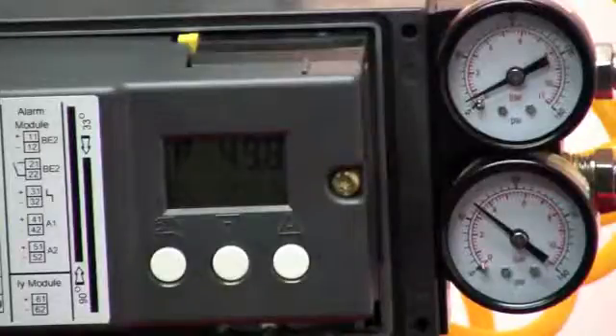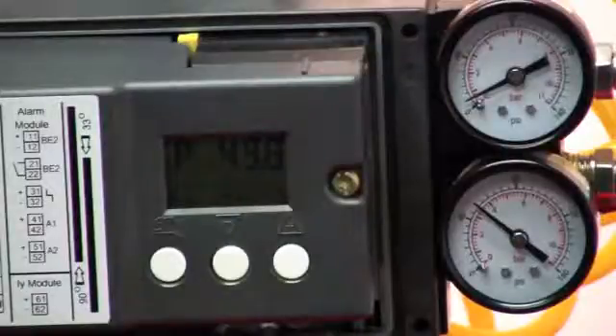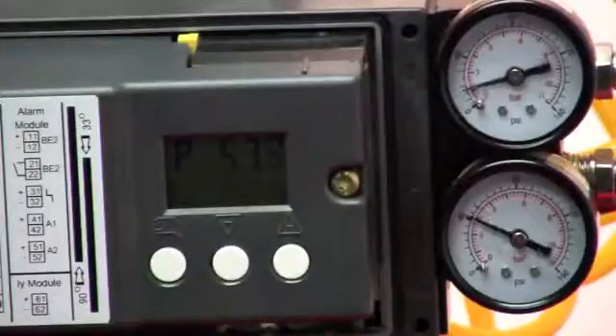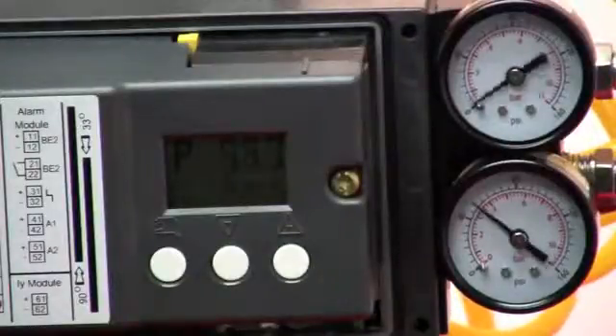Run mode four measures the minimum amount of air required to move the valve at every point during its, along its stroke. And run five optimizes the transient responses.